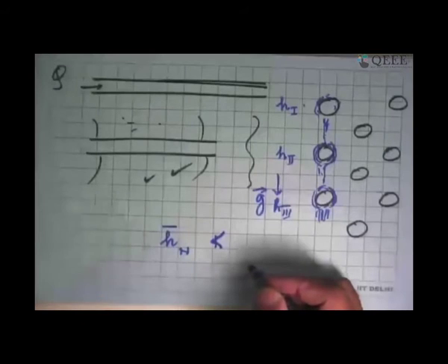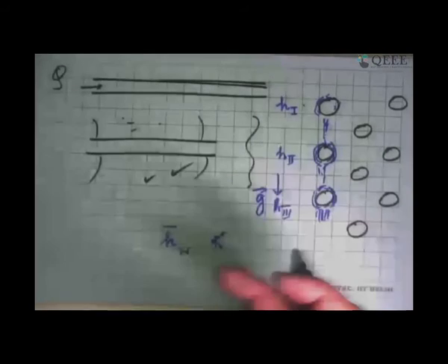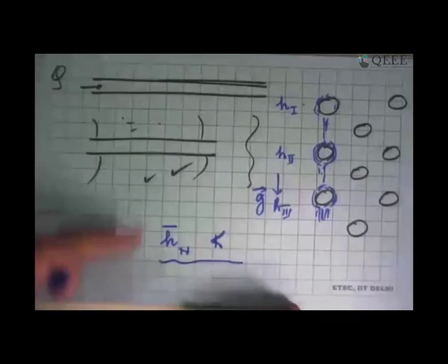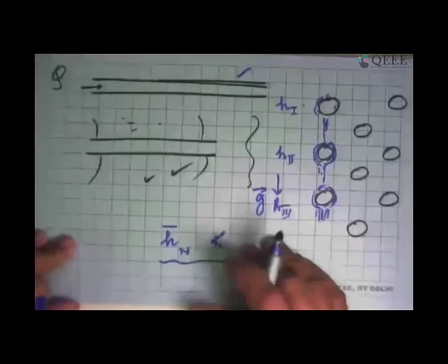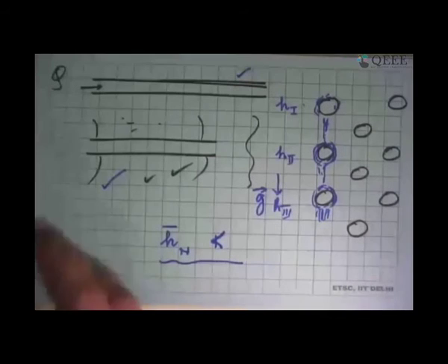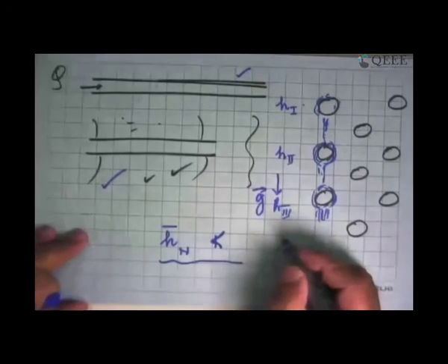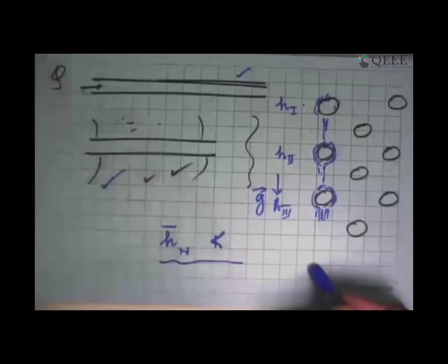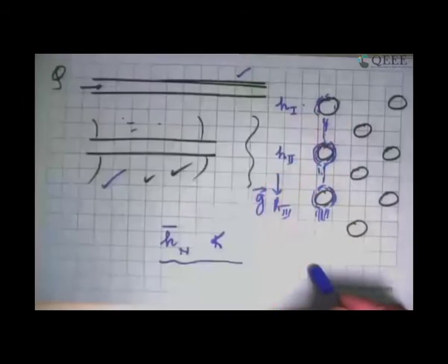So we have to learn to make a trade-off and say, look, this is what's going to happen. Find what's the next best thing that I can do, and how many tubes should I put, and we'll design the condenser that way. So to answer your question, for smaller applications, we are okay with condensation inside tubes. For larger applications, at least for refrigeration cases, we go for condensation outside tubes. But this is something which is there, and for this, we have to have a modified form of the Nusselt number, and that I will give in the sheet, where you can say that if it was only one tube, and this was the Nusselt number, and now I have 9 tubes, one below the other, what is the average Nusselt number in that? So that we can get from there.